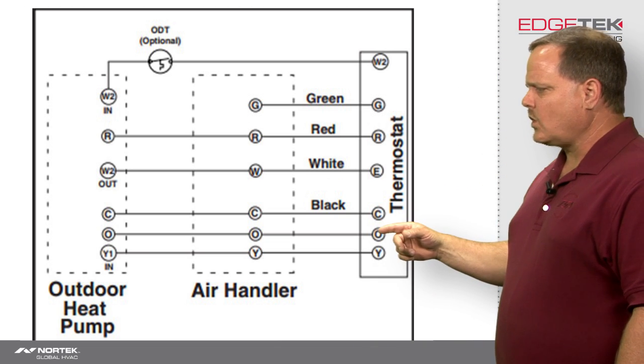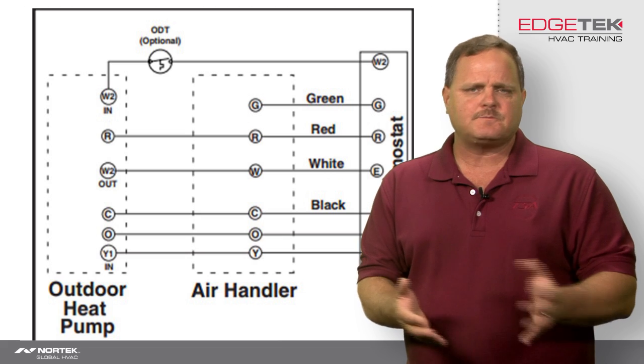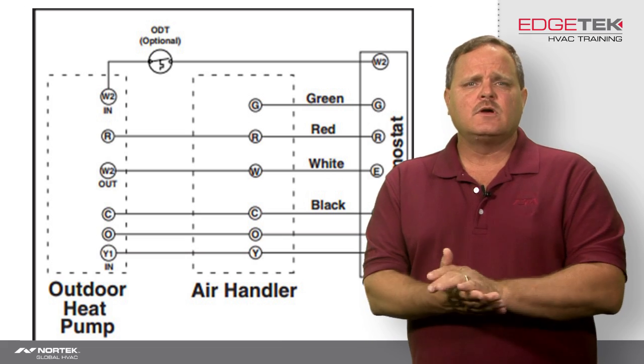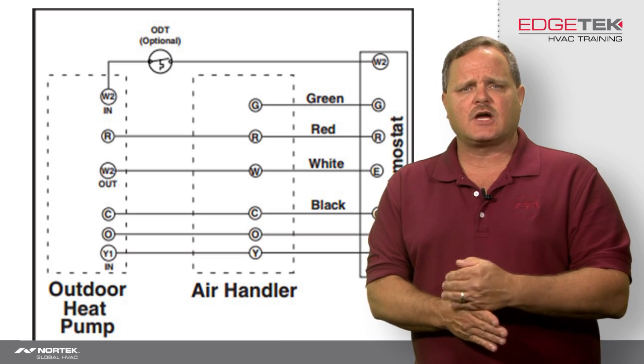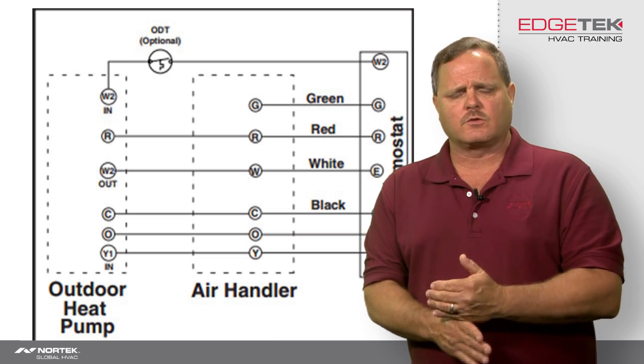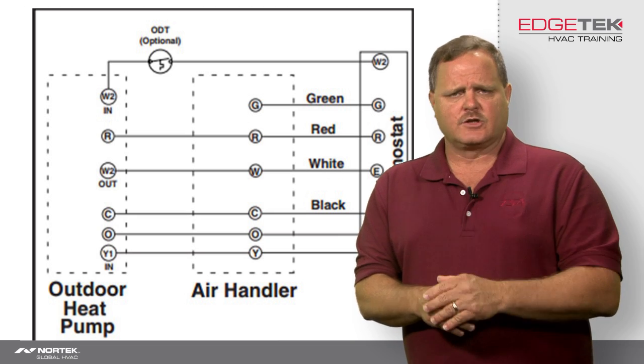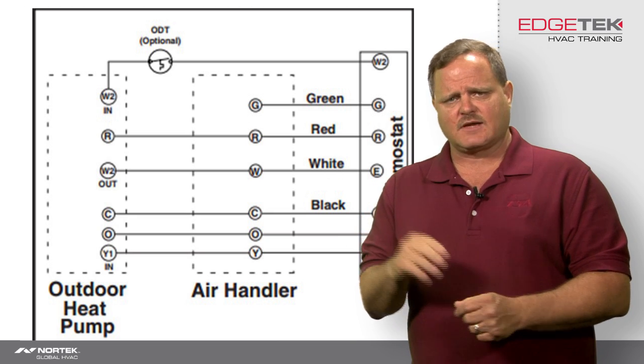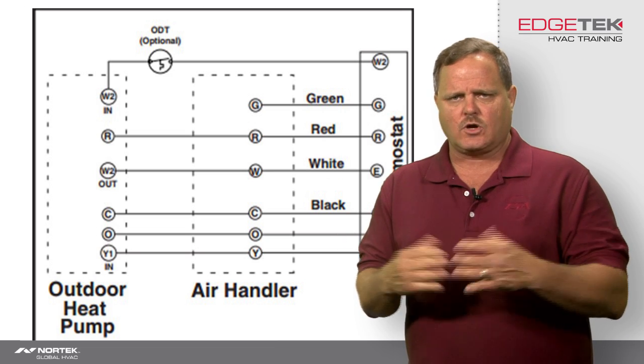But then you have this O terminal. On some thermostats it might be O/B — no big deal. You just need to go into the installer's program and make sure you set that up to energize the reversing valve in the cooling mode, because all of Nortek Global HVAC's heat pumps are energized in the cooling mode. So every time you flip the system switch to cool, that reversing valve should be energized — O should be hot.